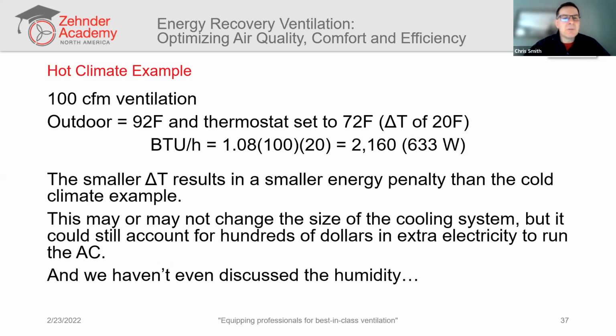Look at a hot climate example. Let's use a similar scenario, but switch the outdoor temperature to 92 instead of 72. So now our delta T is 20 degrees. If we run the same calculation, we arrive at 2,160 BTUs per hour, or a little more than 0.6 kilowatts. This may or may not change the size of the cooling system, but it's definitely going to change how much that cooling system operates. And it can account for hundreds of dollars in extra electricity to run the AC. And that's just the thermal side.